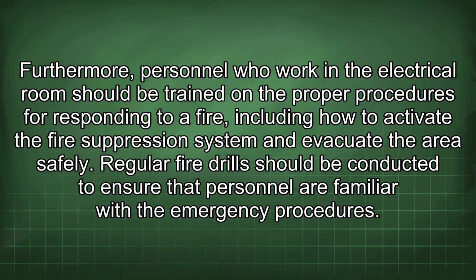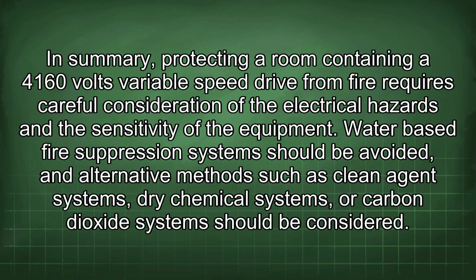Regular fire drills should be conducted to ensure that personnel are familiar with the emergency procedures. In summary, protecting a room containing a 4,160 volts variable speed drive from fire requires careful consideration of the electrical hazards and the sensitivity of the equipment. Water-based fire suppression systems should be avoided, and alternative methods such as clean agent systems, dry chemical systems, or carbon dioxide systems should be considered.